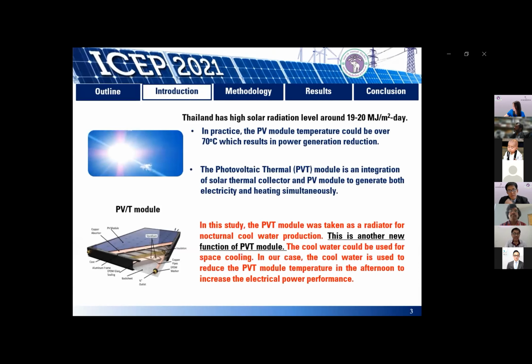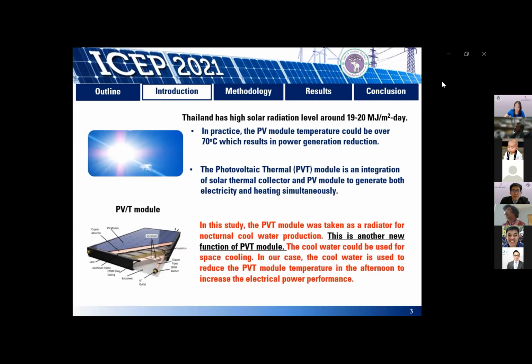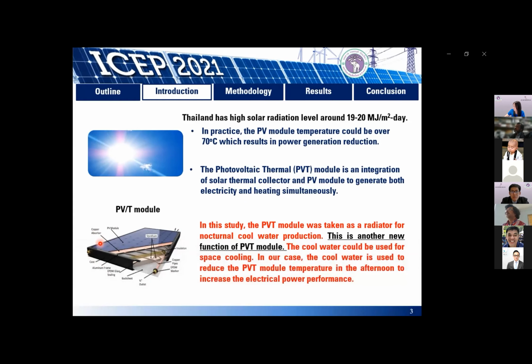Thailand has rather high potential for solar energy, especially power generation from photovoltaics, because Thailand has a high solar radiation level, around 19 to 20 megajoules per square meter per day. However, in practice, the PV module temperature could exceed 70 Celsius, which reduces power generation. So the PV module temperature should be reduced. The photovoltaic thermal, or PVT, module is an integration of the solar thermal collector and PV module to generate both electricity and heat simultaneously.